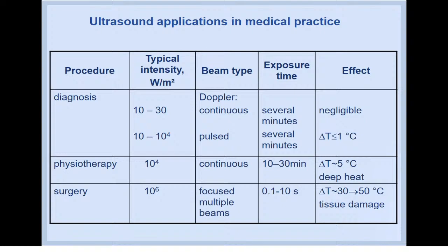For therapeutic purposes, for example in case of rheumatic complaints, ultrasound with a frequency of 0.8 up to 1.2 megahertz and an intensity of a maximum of a few watts per centimeter squared is usually applied. This therapeutic effect is mainly due to a mechanical pulsating effect, micromassage, and heat production.